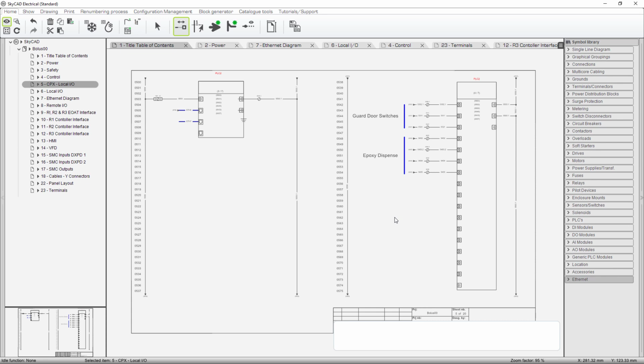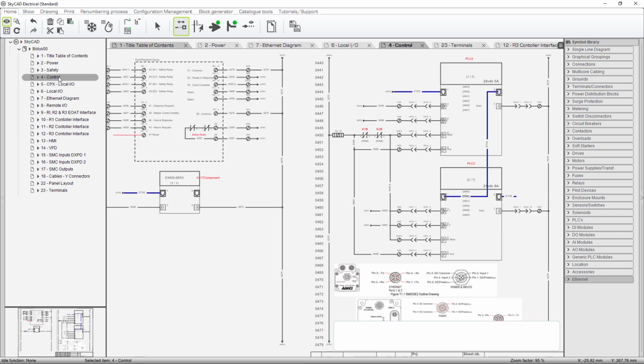So an L27 ERM has 16 in, 16 out, and then it has 4 analog in, 2 analog out, then high-speed counter terminals. They are embedded in the controller. And here I'm showing them as separate boxes. That's just the way you have to draw it. So this is my 16 inputs, discrete inputs. I've got 3 from guard door switches, and then remember our epoxy dispense right here, our outputs?